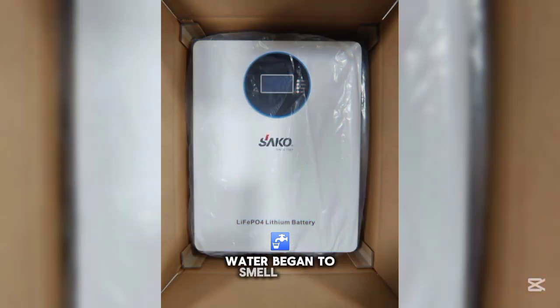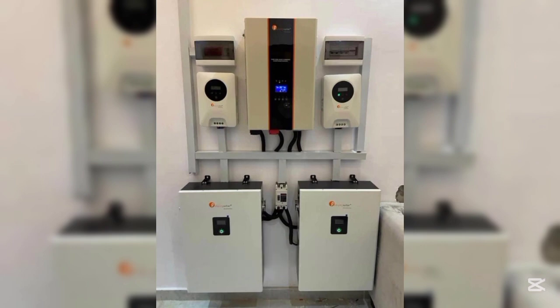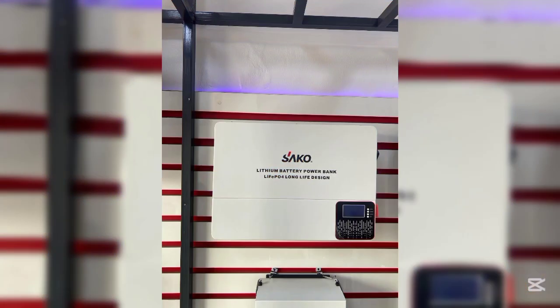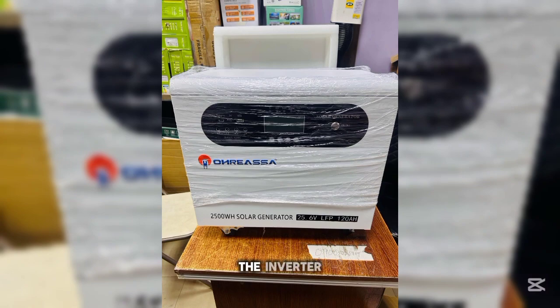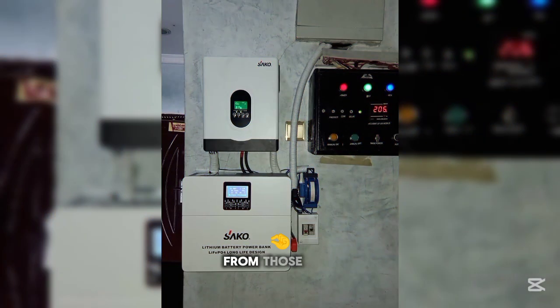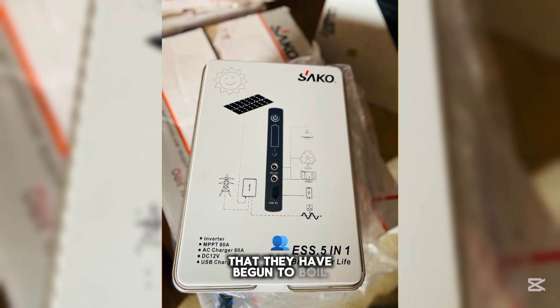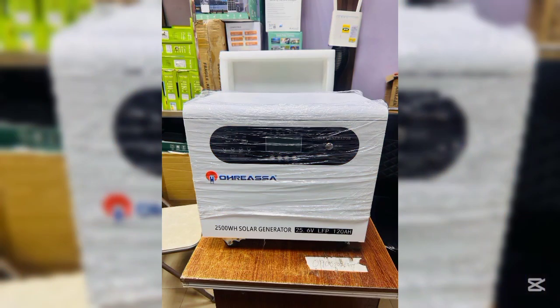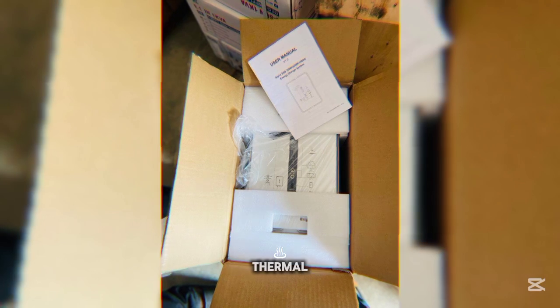The light started flickering. The inverter began to smell like burning plastic. Within 10 minutes, the batteries were so hot that they could fry an egg on them. So what is the reason for this? Because the inverter was pulling so much power from those 2 small batteries that they began to boil internally. They didn't just run out of power, they went into thermal runaway.